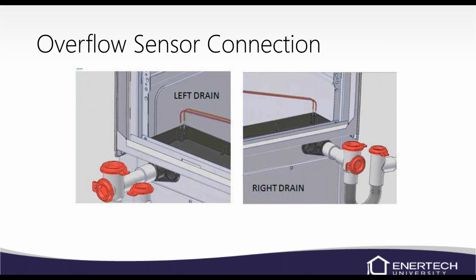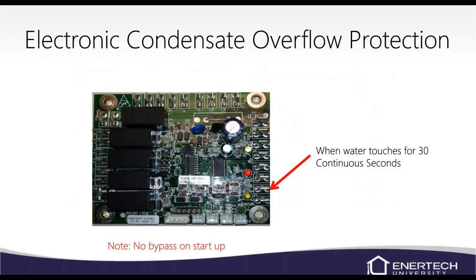And a lot of times I've seen on these little wires that plug in on the spade connectors that at some point the pan has had water in it, and those connectors get a little bit of corrosion on them. So you can take those connectors off and brush them up with a wire brush and put them back on. That seems to take care of the nuisance condensate overflow lockout. If you still have a condensate overflow lockout, you can remove one of the wires here on the board, and then the circuit cannot be completed. So it shouldn't lock out ever on condensate overflow.